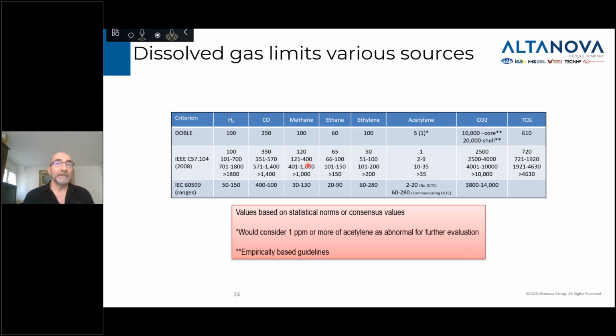The first thing we have is dissolved gas limits. Now, there are different types of criteria that have been developed over the years. I'm just showing here three of them that are mostly used around the world. You have the Doble criteria for the maximum level of gas that you should find in transformers in normal operation. You have the IEEE C57.104-2008, and you have the IEC 60599. Frankly, the majority around the world use the IEEE C57.104-2008 as a standard.